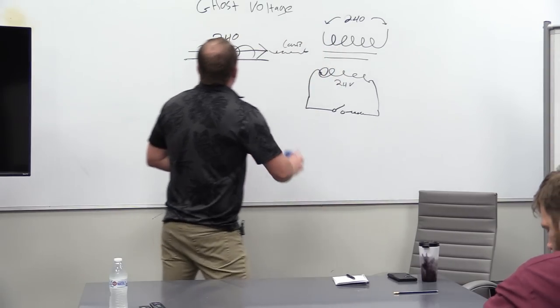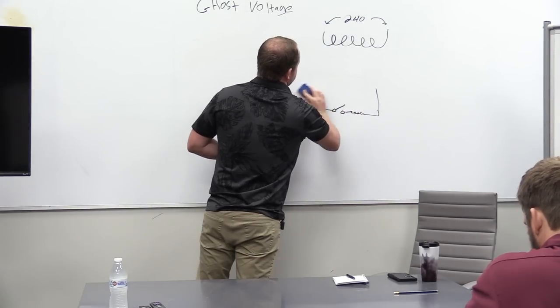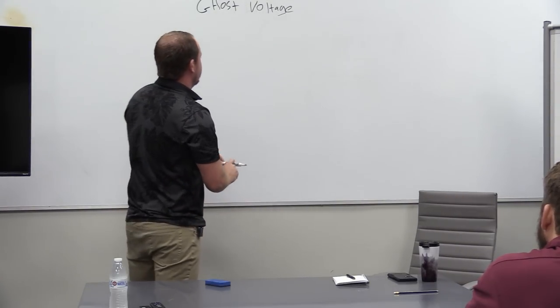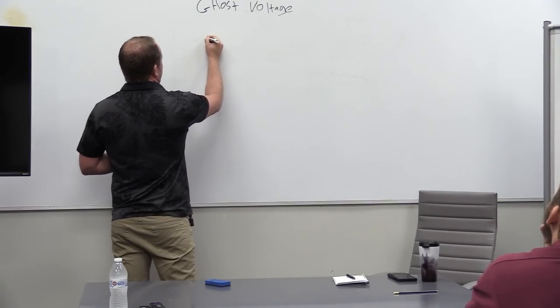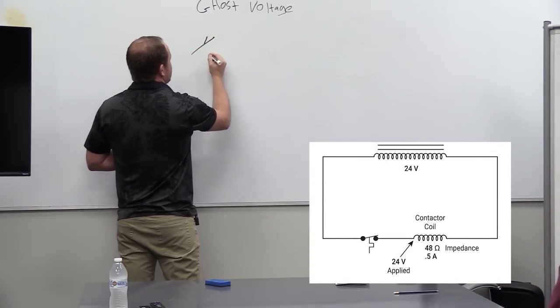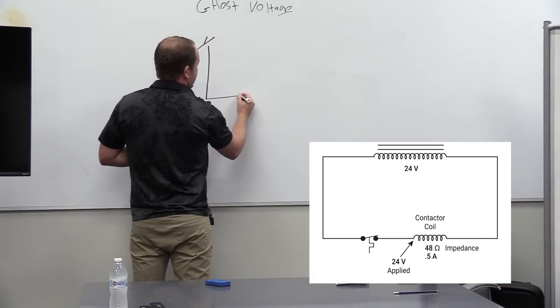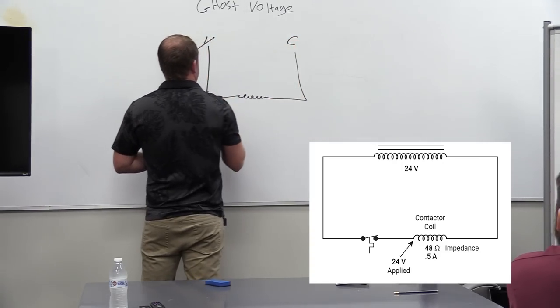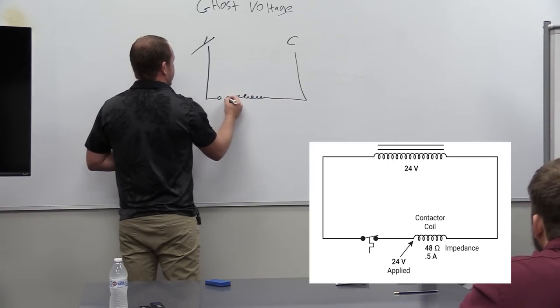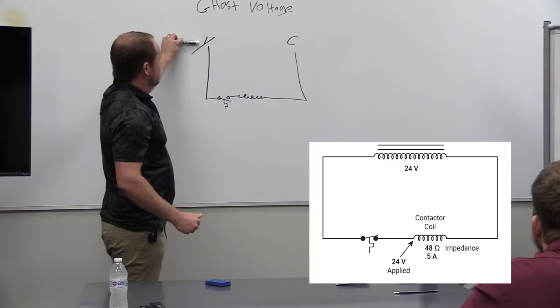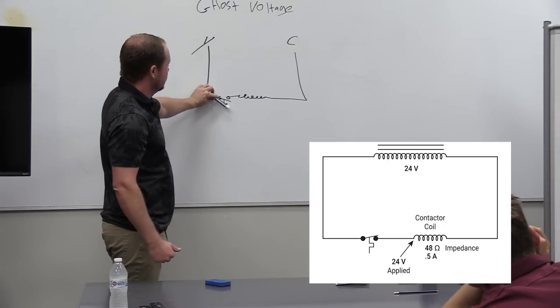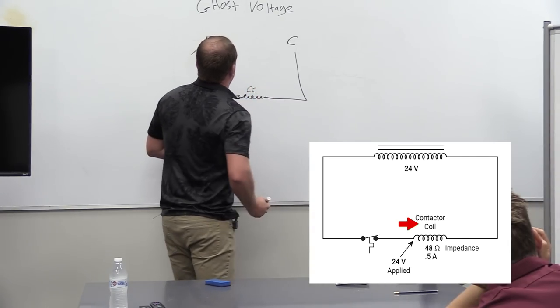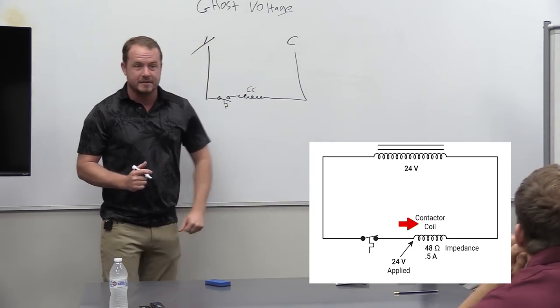But there's another reason why we see ghost voltage, and it's actually a more common reason. We'll draw a really basic circuit here. So we're going to call this our Y circuit. This is our Y circuit. And then it goes back over to common. We'll draw a switch in here. This is our thermostat. Call for cool, right? When there's a thermostatic call for cool, the temperature increases, causes the switch to close, which then energizes our contactor coil, right? And our contactor coil is connected in between Y and C.